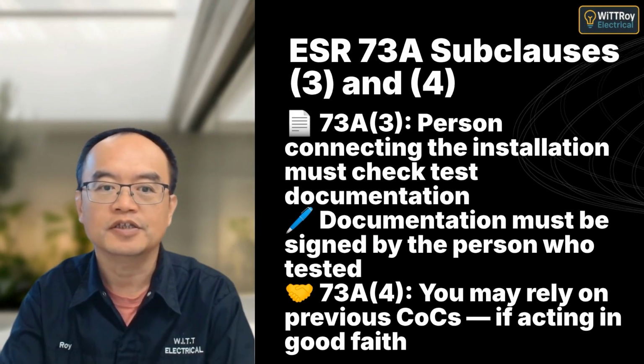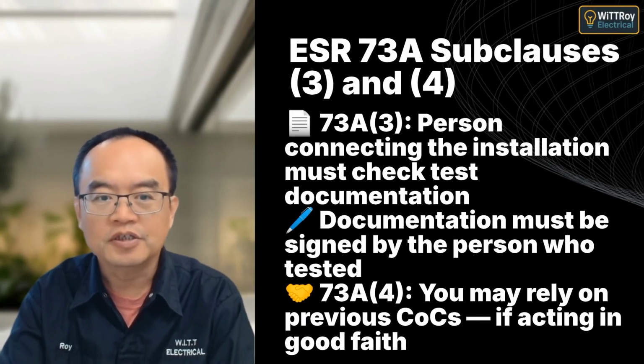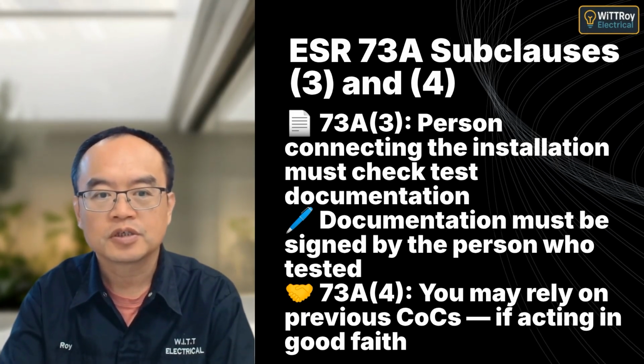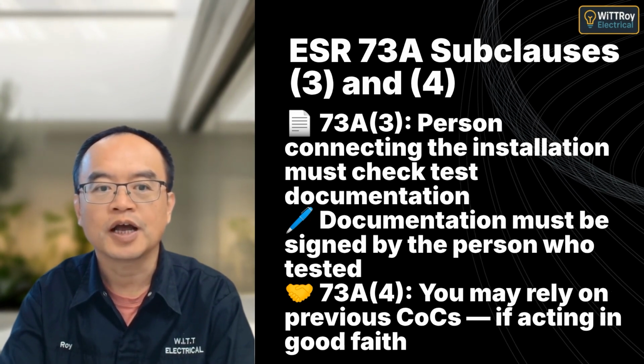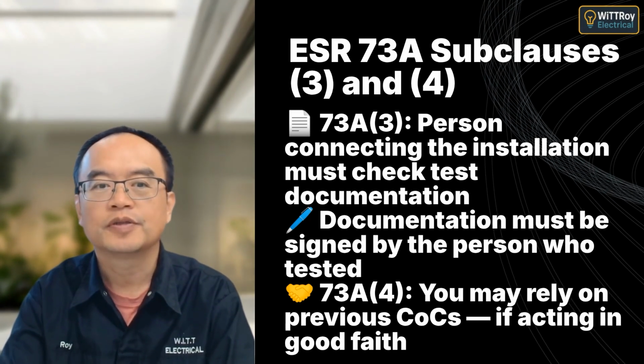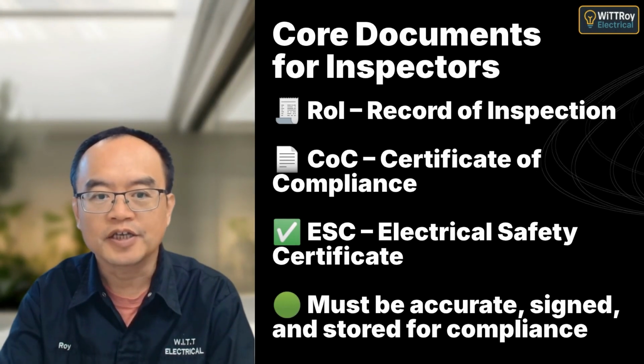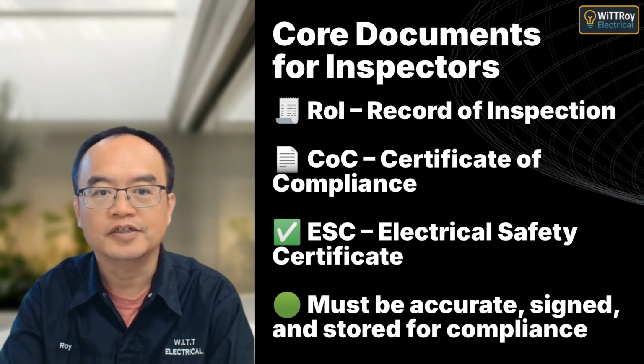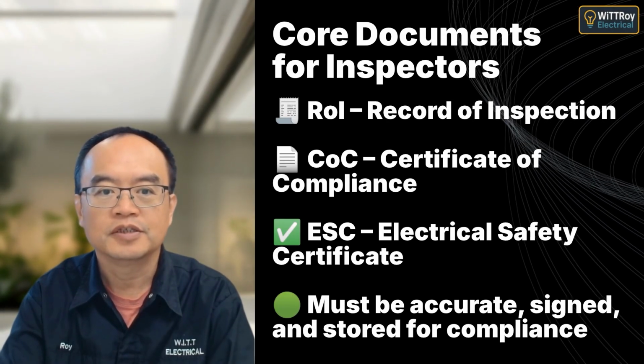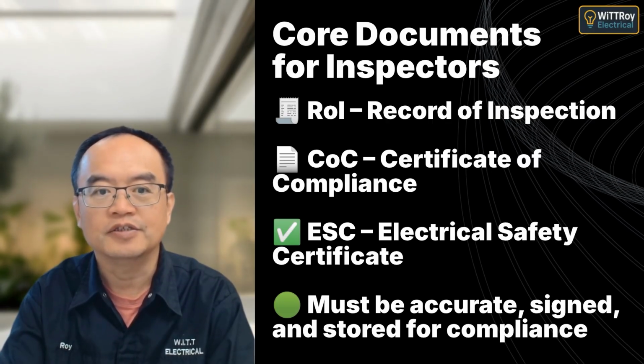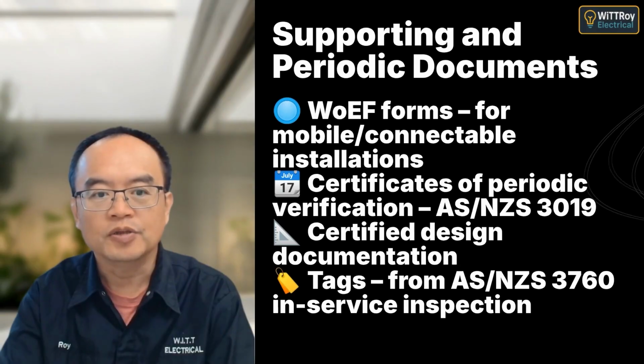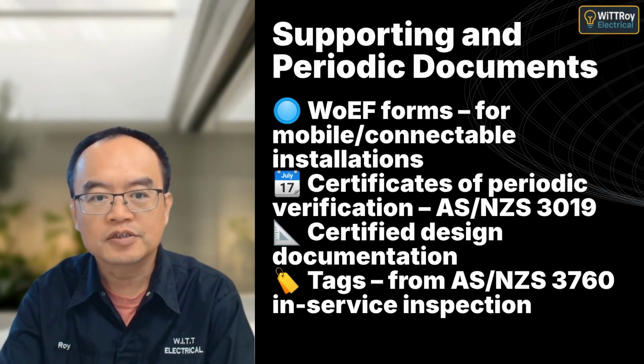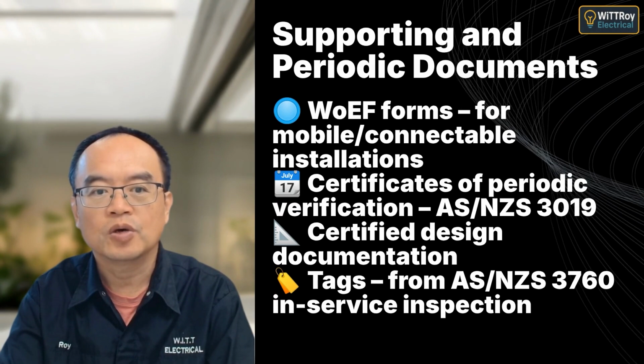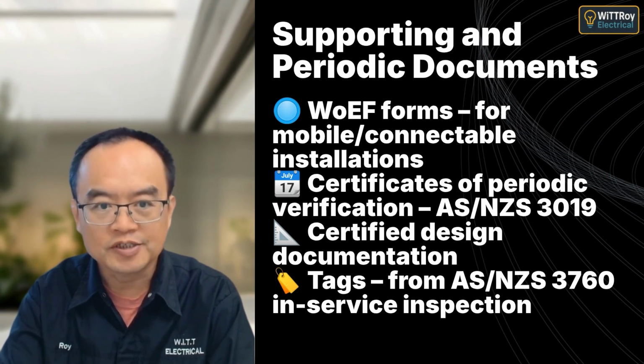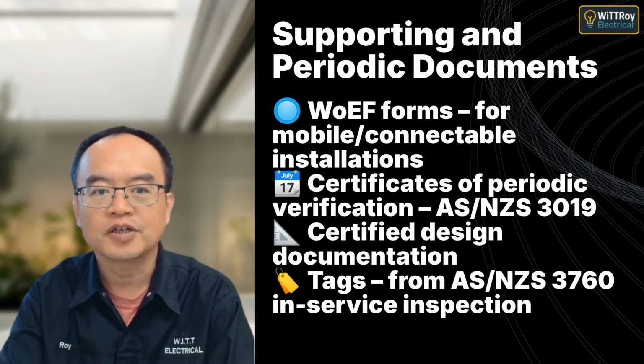If the person connecting the installation didn't do the testing, they must sight signed documentation stating what was tested and the results. ESR 73A4 allows you to rely on existing COCs, but only if you act in good faith and reasonably trust their accuracy. ROI, COC, and ESC are essential documents. As inspectors, we must ensure they are properly completed and reflect the actual work and safety verification done. Supporting documents include WOEFs for mobile setups, certified designs, and periodic certificates for older or temporary installations. Inspectors must also understand test tagging under AS NZS 3760.